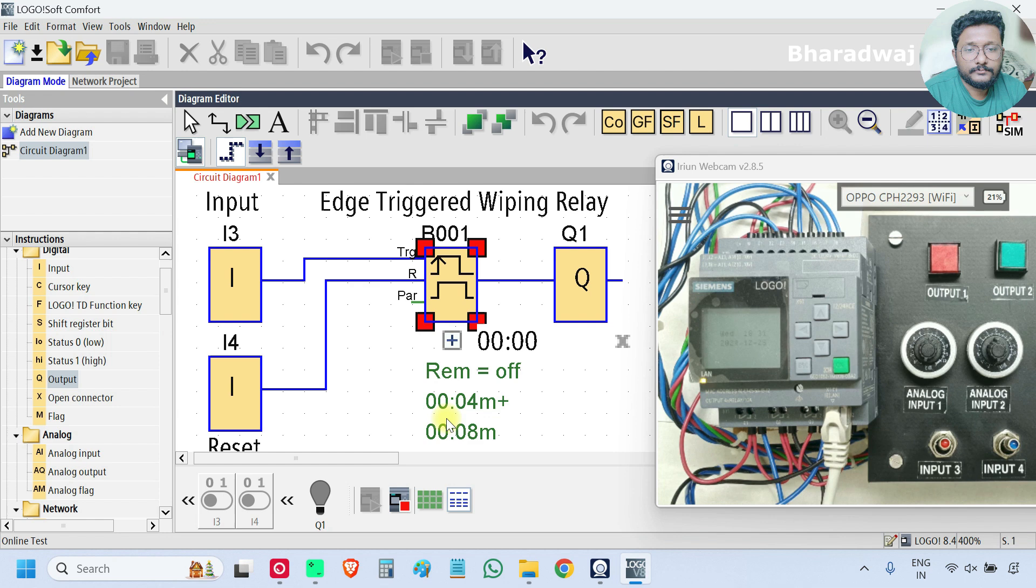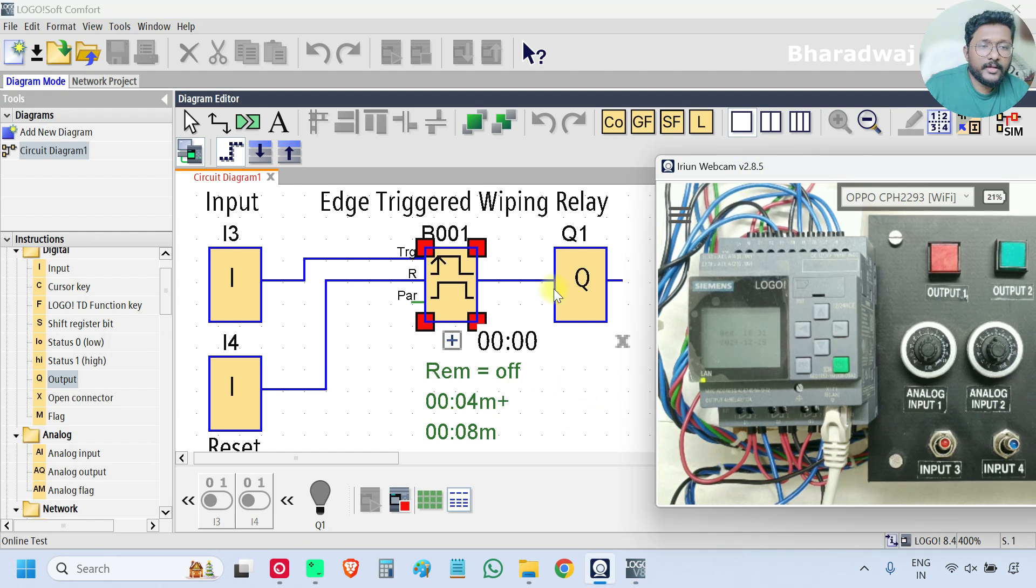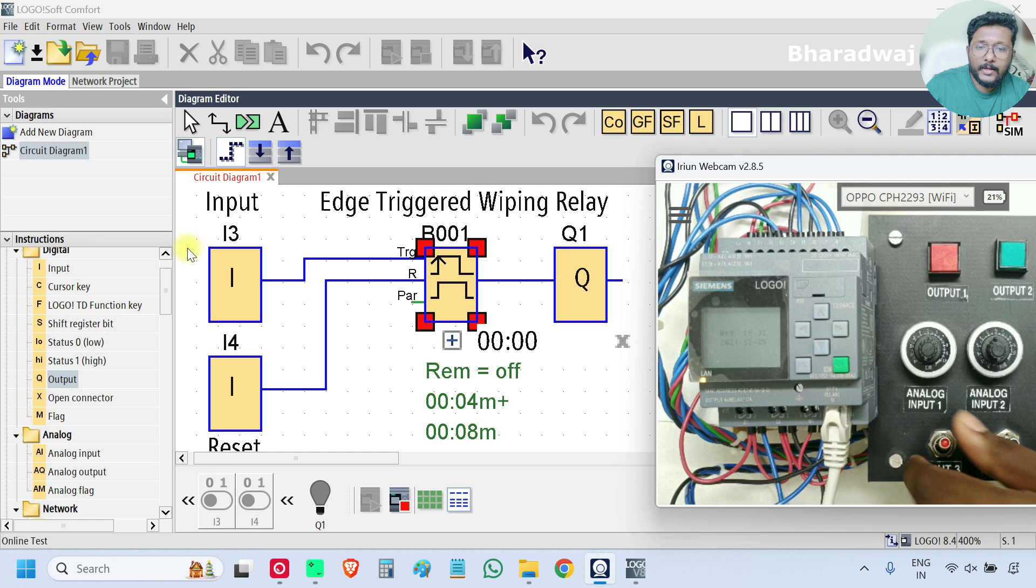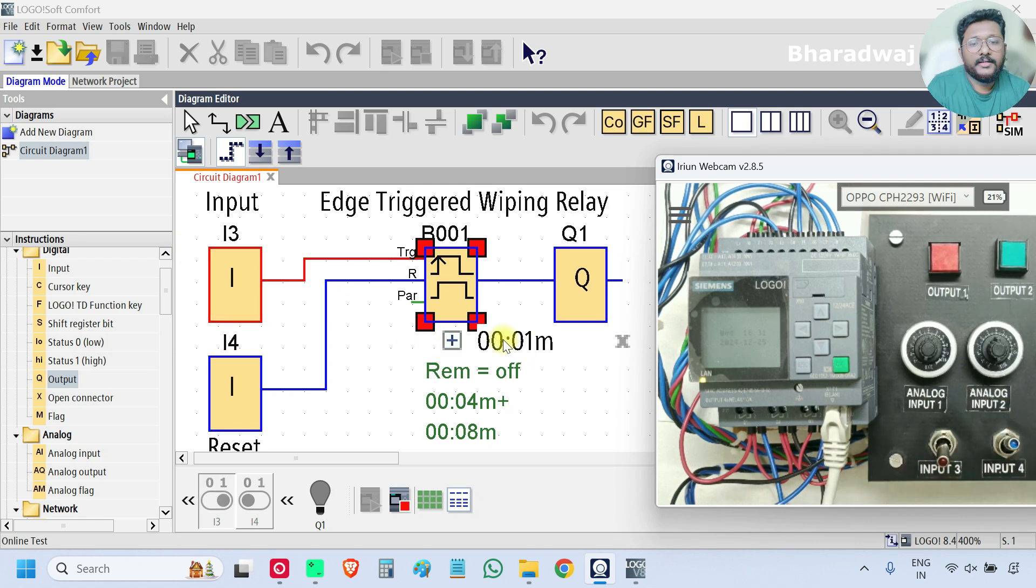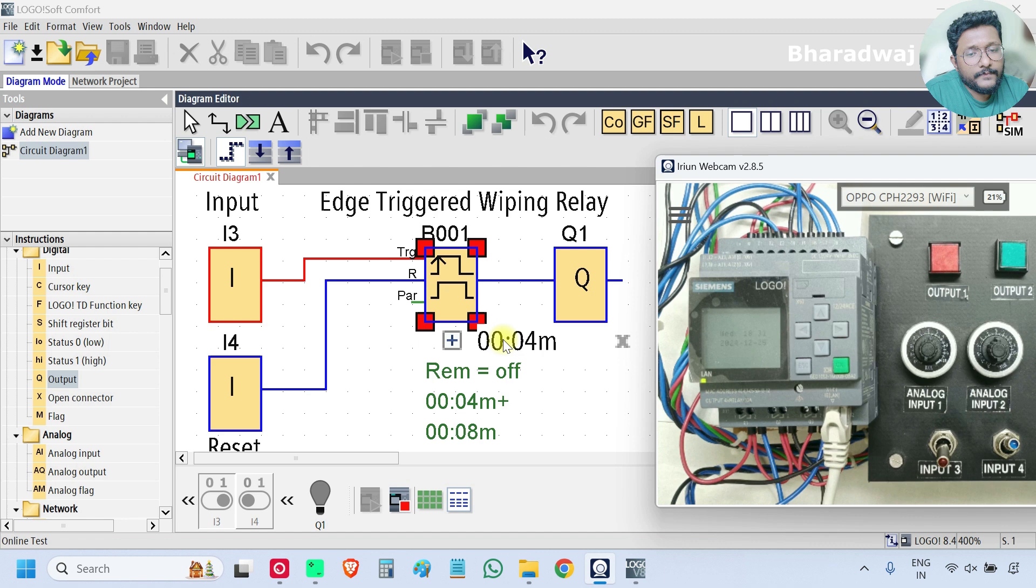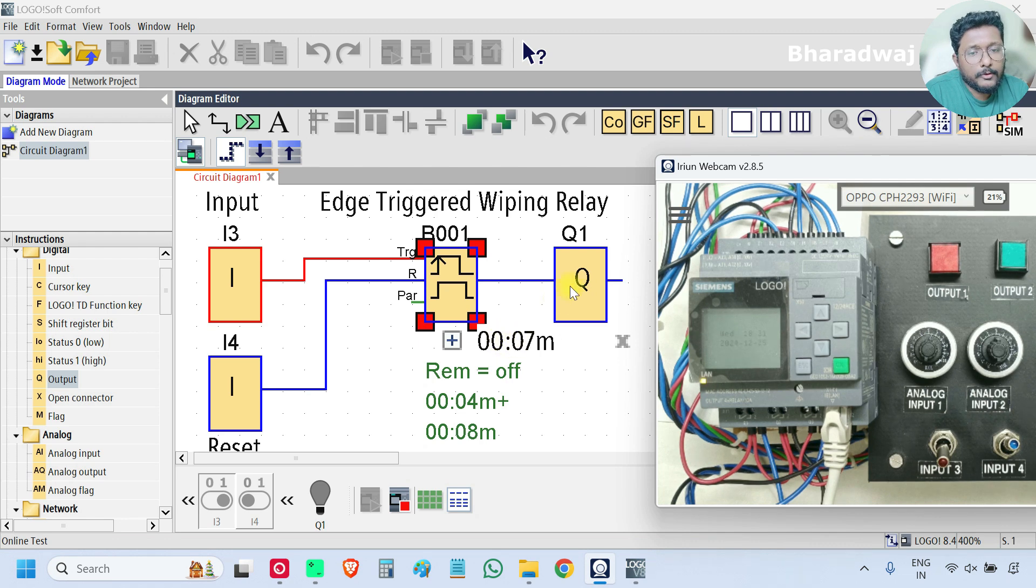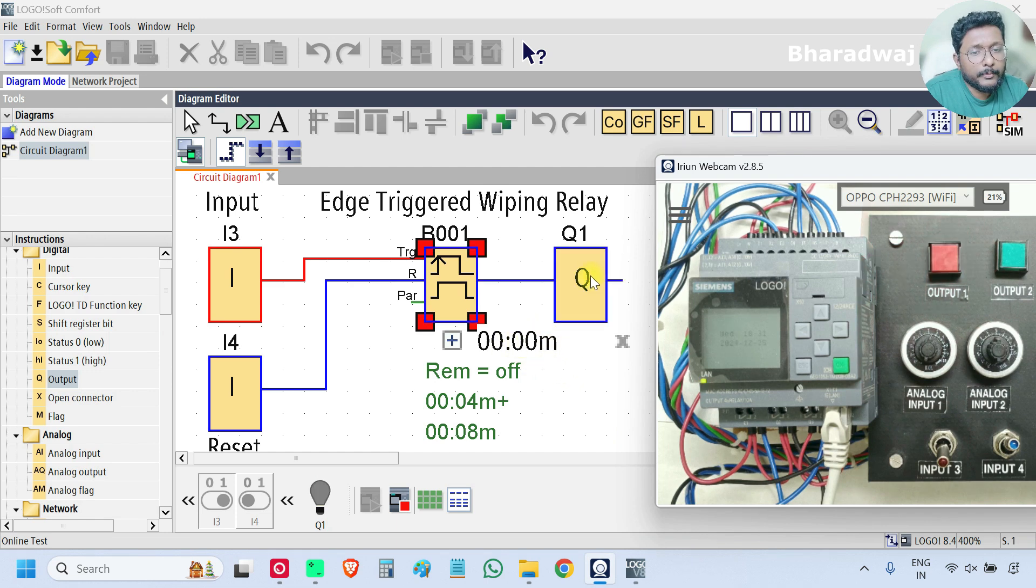Now I will turn on the input i3. Observe the timer. The timer is started. First the eight seconds is running, output is off. Next the four seconds timer is running, output is on.